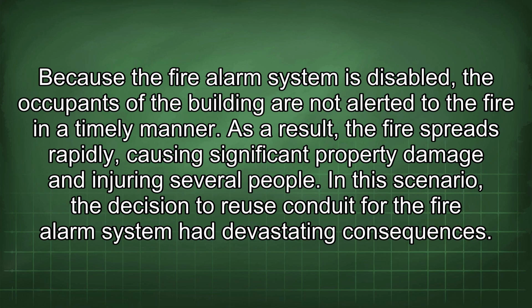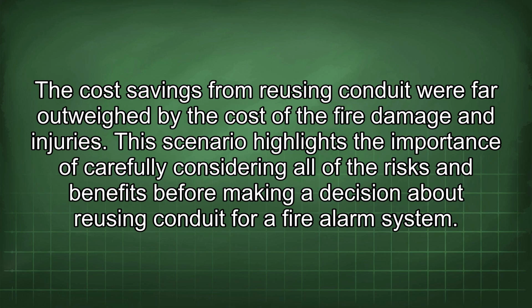Because the fire alarm system is disabled, the occupants of the building are not alerted to the fire in a timely manner. As a result, the fire spreads rapidly, causing significant property damage and injuring several people. In this scenario, the decision to reuse conduit for the fire alarm system had devastating consequences. The cost savings from reusing conduit were far outweighed by the cost of the fire damage and injuries. This scenario highlights the importance of carefully considering all of the risks and benefits before making a decision about reusing conduit for a fire alarm system.